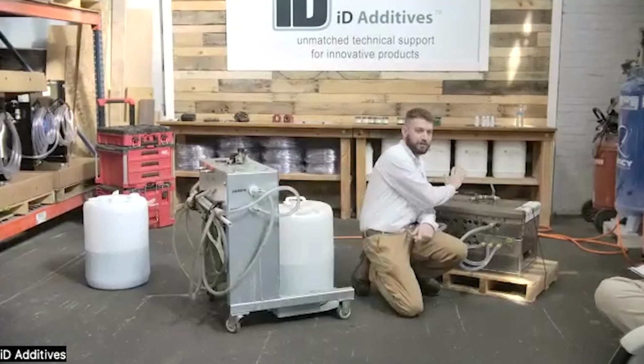So if I am plumbed into my blowout side and set to my pump, it's just not going to work because of those one-way check valves. So I always hook up to blowout air first. I turn to my blowout side and I turn it on. You can hear it kind of drumming up that water. I don't see any water coming out of the mold. So I'm safe to set over to my pump air side, swap my 3-way valve, and I slowly turn it on.